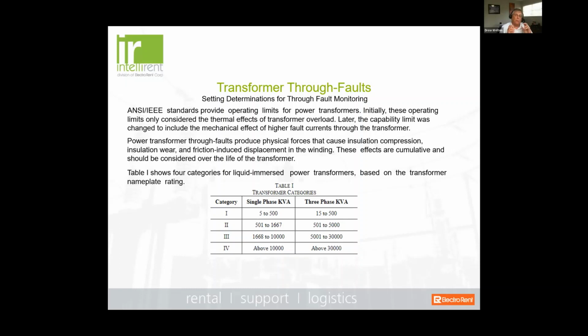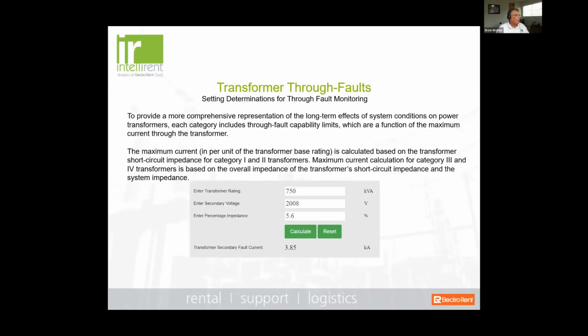Now, what does that mean for your protective relaying? Well, if I have a digital relay that I'm replacing, or I'm bringing in a new protective relay, then the information from the old relay should be brought into the new relay, because this is cumulative over time. We want to see how many through faults that transformer has been subjected to. Okay, now there are some calculations out there that will help you determine what the through fault withstand capabilities are and how to set the alarm.